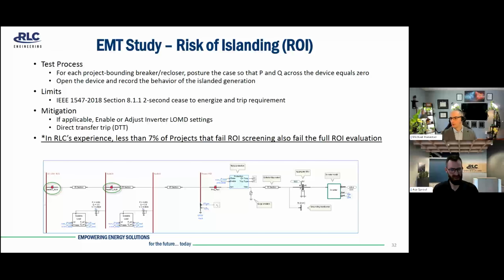So LOMD settings in particular, if we have access to them, it's usually just, can we enable them or disable them? And we would just enable them in this case. However, we have had success in the past reaching out directly to manufacturers through our contacts and getting them to make tweaks to these settings and update their models, provide us with new ones, and then we can retest. Now, I would say if they do anything to mitigate ROI in this case, they would also need to implement that into their firmware for their field installation, so we're not simulating something that's not going to be available in real life.